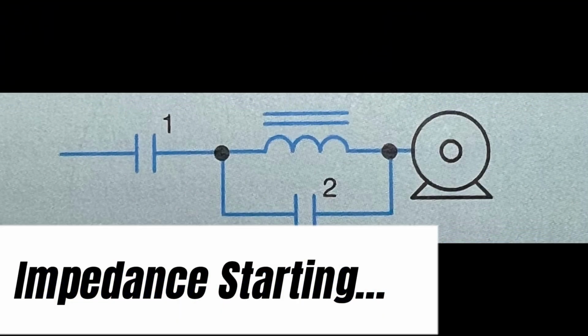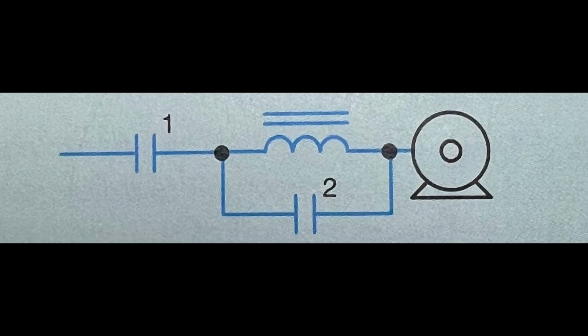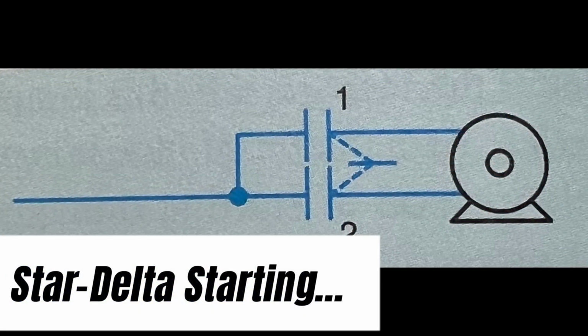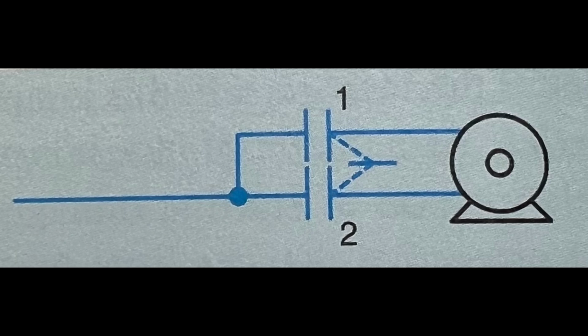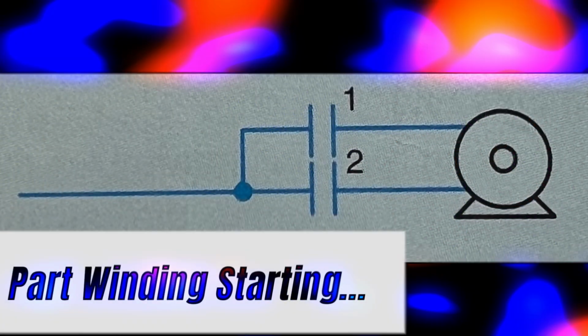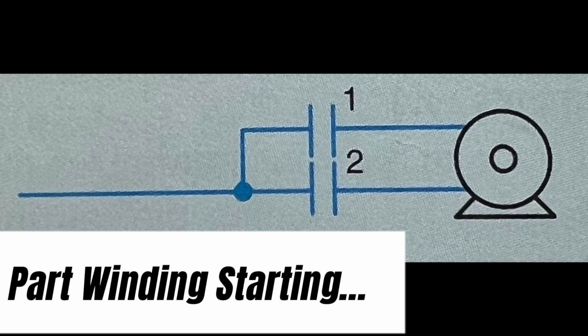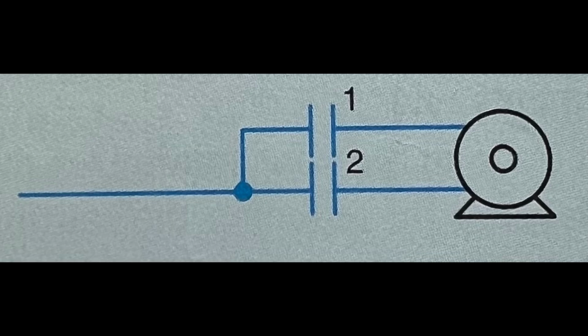Next, impedance starting. Reactors are used in series with the motor. Next is star delta starting. The stator of the motor is star connected for starting and then delta connected for running. Next is part winding starting. Stator windings of the motor are made up of two or more circuits. The individual circuits are connected to the line in series for starting and in parallel for normal operation.